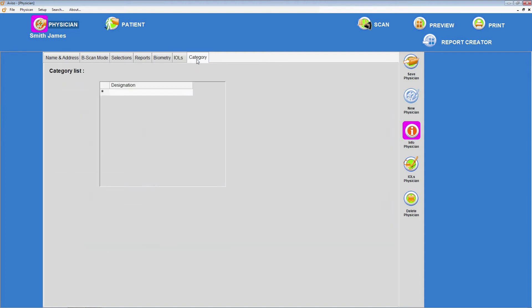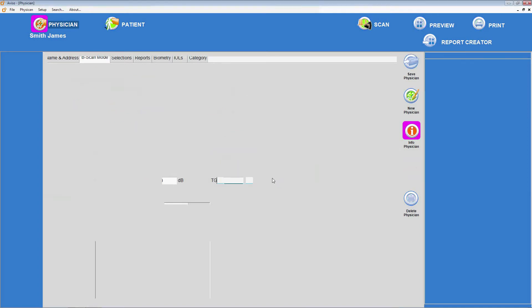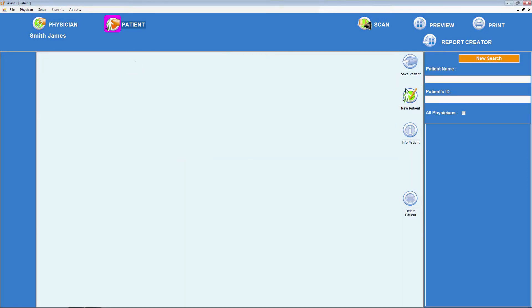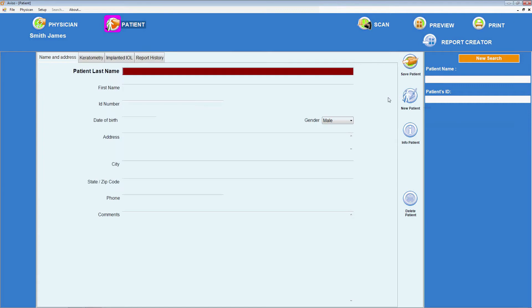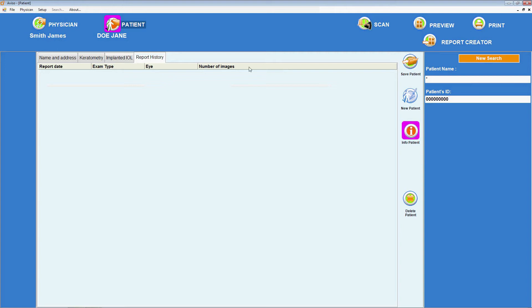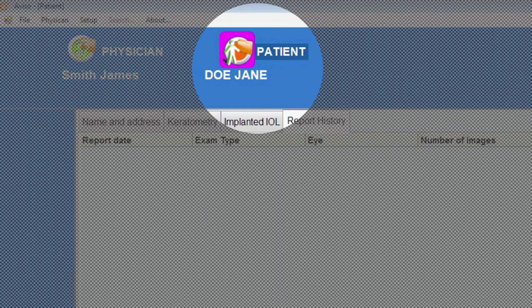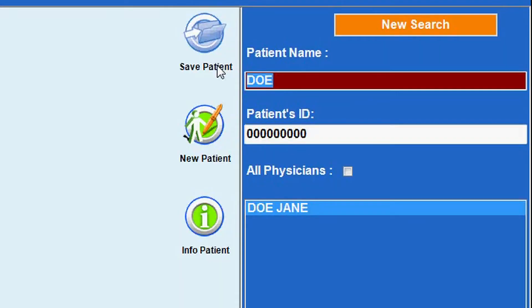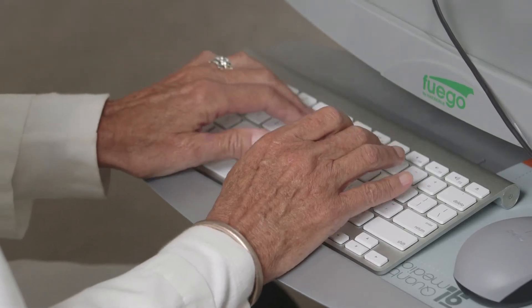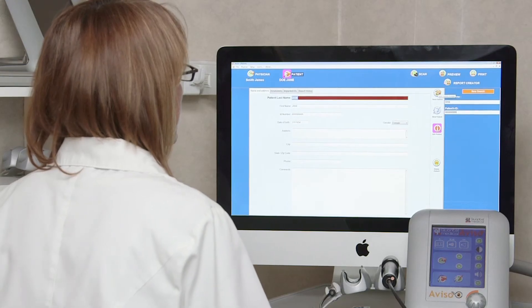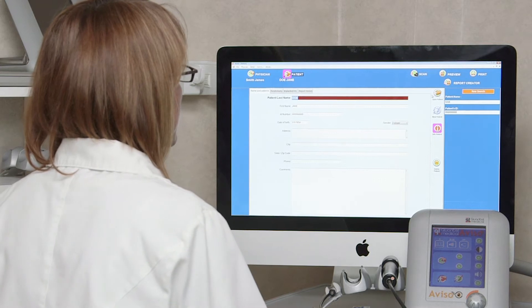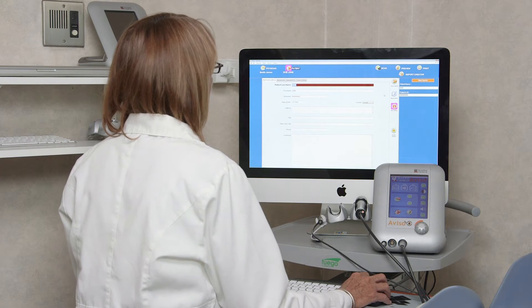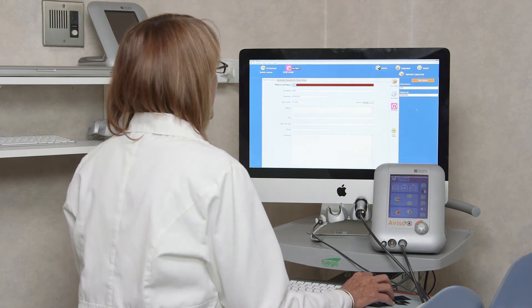Once a physician has been entered into the system and saved by pressing the Save icon, a new patient can be added via the New Patient icon. Name and address, keratometry data, and other important history details can be input and saved. A returning patient can be found via the Patient icon, searching with the initial letter of the patient's last name in the Patient Name field. Alternatively, typing a star or percent sign into this field will bring up a list of patient names to choose from. When the All Physicians checkbox is selected, this list will include patients input by all physician users. Once a patient has been selected, his or her previous exams and IOL calculations can be viewed from the pull-down menus.